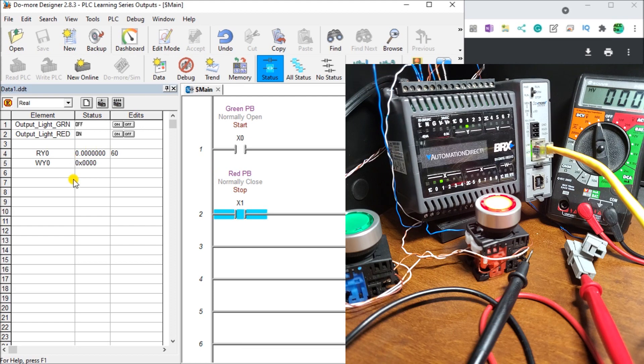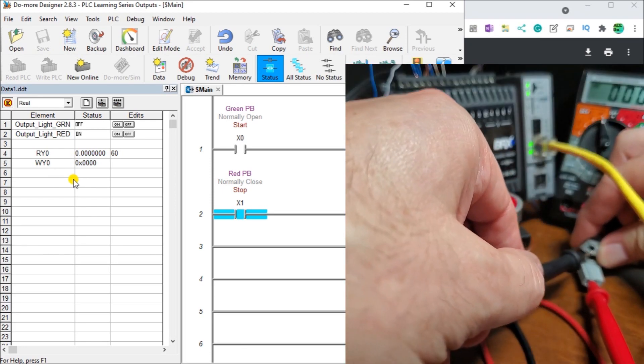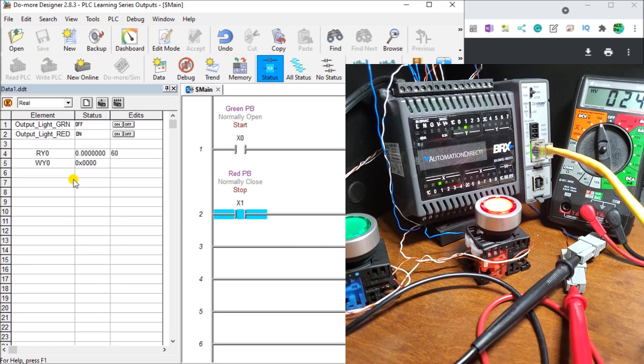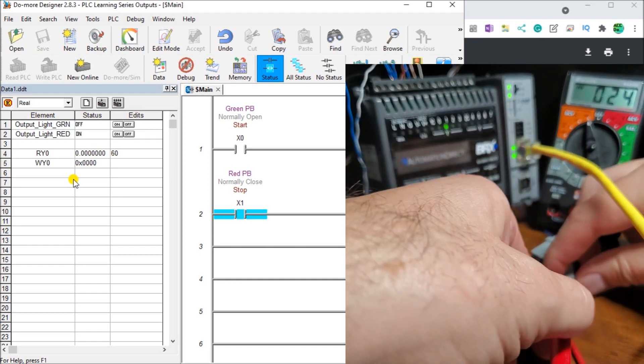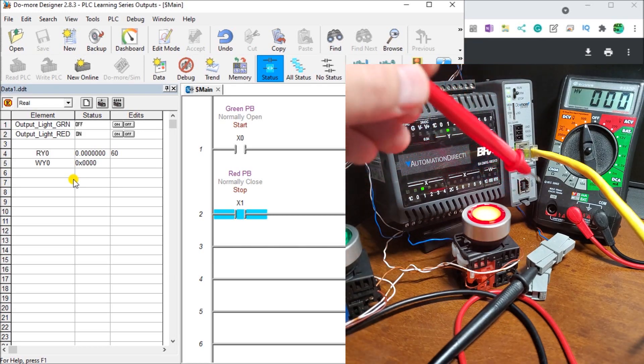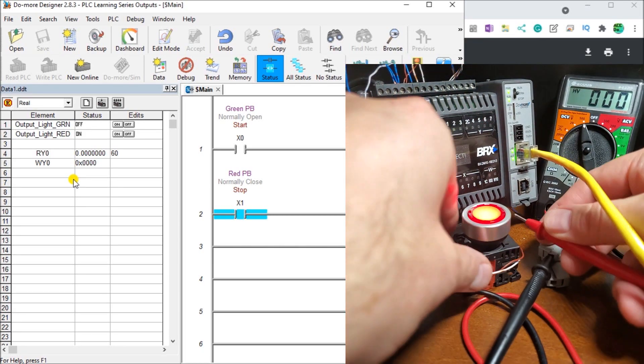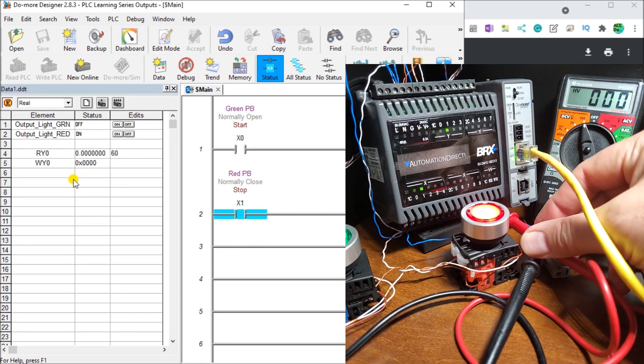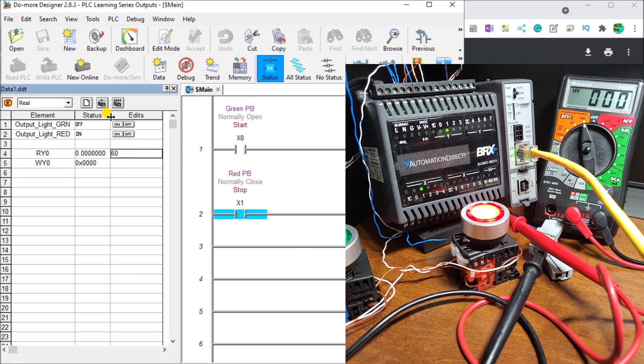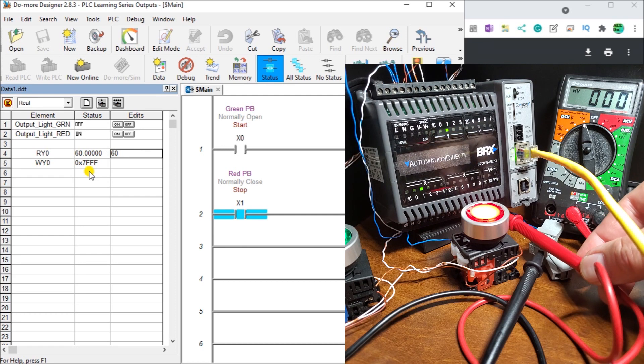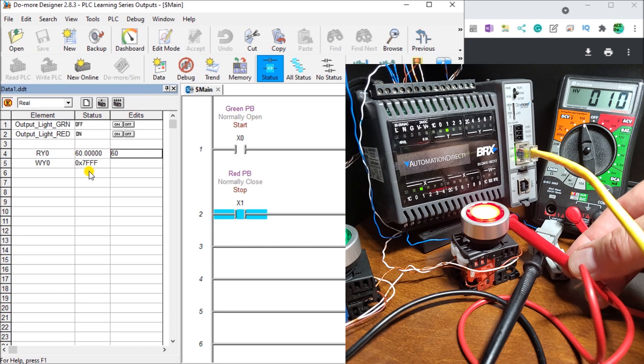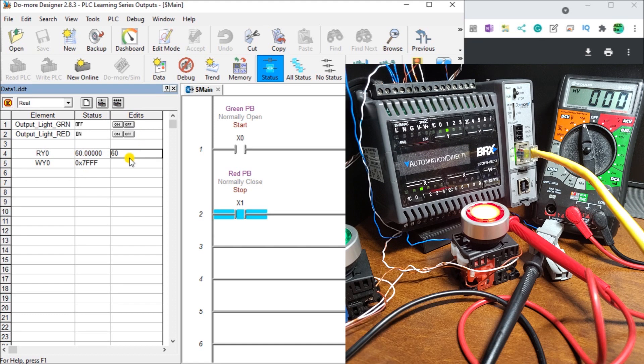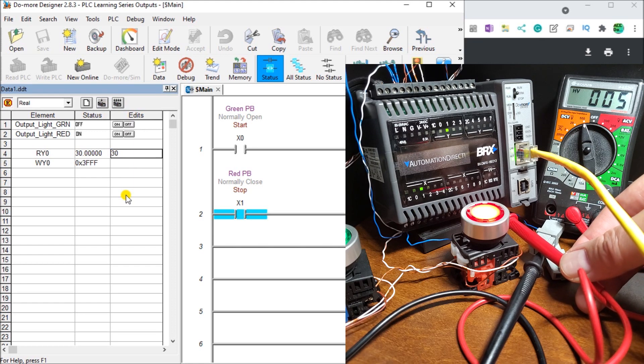Let's take a look at our analog output. We plug in our negative and confirm we still have our 24 volts. Taking the positive lead and attaching it to our analog output, you can see right now we have zero volts. Now let's write in 60 to represent 60 hertz — you can see it automatically goes to a higher number representing our 15 bits. Hitting the output, you can see we now read 10 volts for our analog output. We can do anything in between — putting in 30 should give us half the output range, representing 5 volts. Checking the output, and that's exactly what it's doing: giving us a 5 volt output.